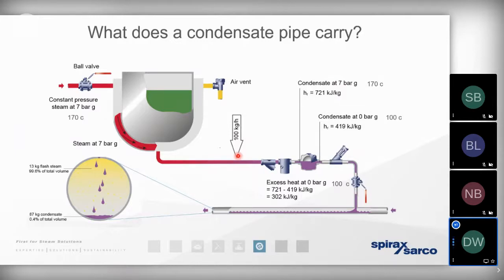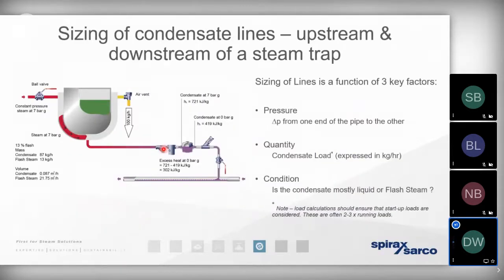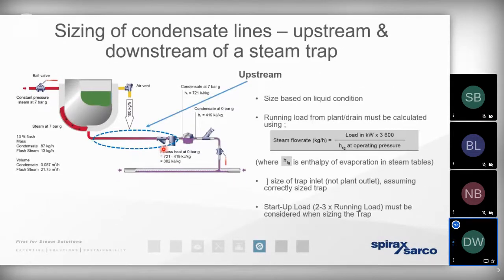So it's relatively easy to size the pipework at this point. We size it on water as a liquid. But the only thing to bear in mind is that just as it's good working practice to size a steam trap on the distribution pipework to allow for that higher warming up load, we want to apply the same rule of thumb when it comes to removing the condensate away from the process. So typically we allow a safety factor. We want to allow for approximately 3 times more condensate to be removed from the process. In other words, we'll multiply that 100 kilogram per hour running load to allow for a warming up load of say 200, maybe even 300 kilograms per hour.